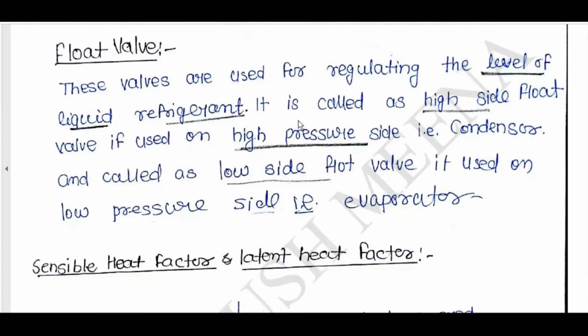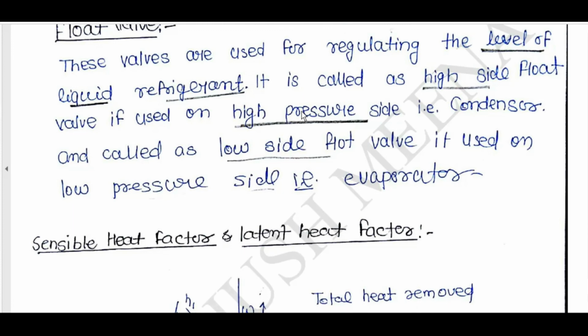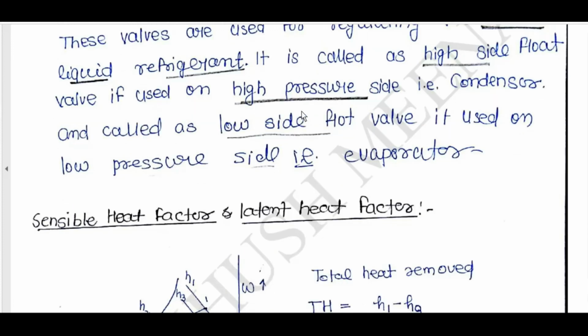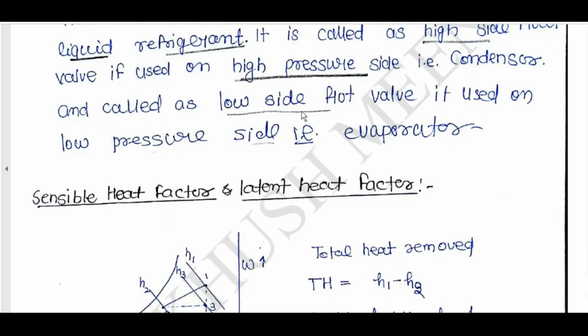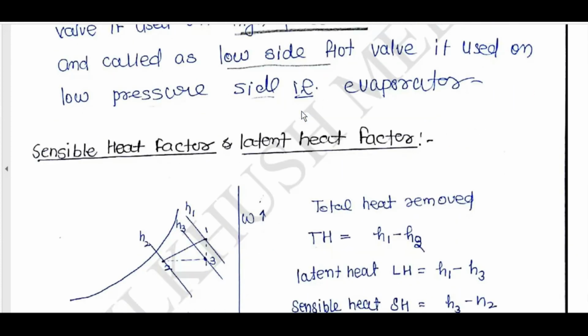Float valves are used for regulating the level of liquid refrigerant. It is called a high side float valve if used on the high pressure side, that is the condenser, and a low side float valve if it is used on the low pressure side, that is the evaporator.